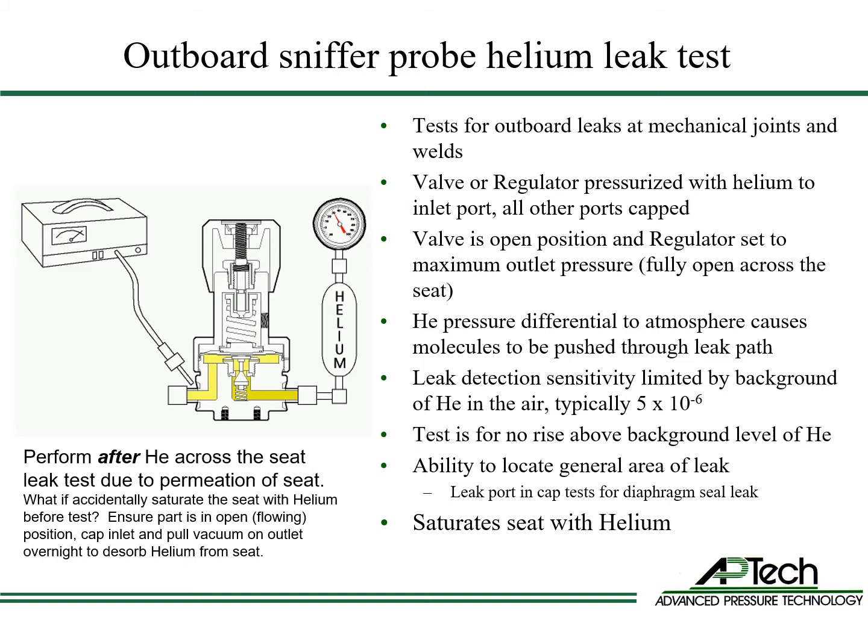The outboard sniffer probe helium leak test is used to test for outboard or external leaks. This method pressurizes the inlet port of the valve or regulator with helium while the device under test is fully open across the seat. The differential pressure between the part's internal cavity and atmosphere surrounding the part pushes the helium through the leak path, and the sniffer probe vacuum pulls the helium from atmosphere into the detector. APTech tests all mechanical joints and welds. The leak sensitivity is limited by the concentration of helium in the atmosphere, or about 5×10⁻⁶, but this concentration varies. The part passes if the sniffer probe does not detect a rise above background levels of helium. This test has the ability to locate the general location of the leak using the sniffer probe. Because this test saturates the seat with helium, it must be done after a helium across-the-seat leak test to avoid saturating the seat with helium.